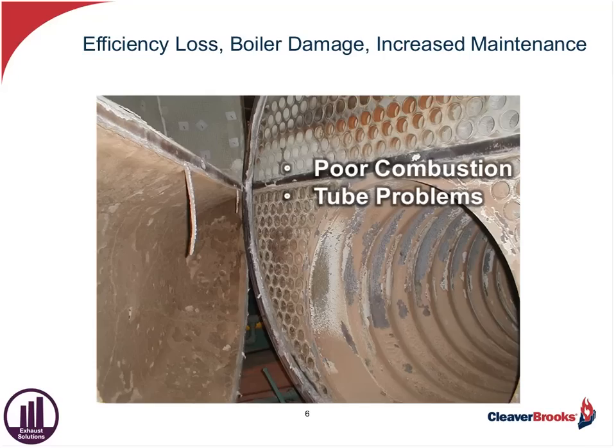Here you see a boiler. We took a picture of this. This boiler was in excellent condition. As a matter of fact, about a month or two before this boiler was opened, and you see what you see here, it was tuned up. Proper fuel-air ratio, everything was fine. You can take a look at the rear door here. There's no signs of cracking or anything else. This boiler was well maintained, and it was tuned up.